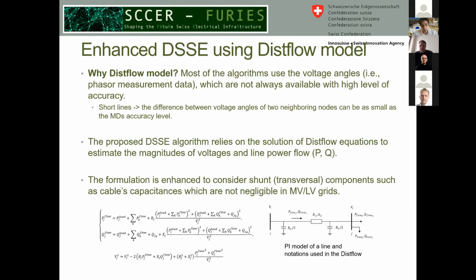The problem is that in low voltage networks, the lines are quite short, so the phase angle difference between two neighboring nodes can easily reach the accuracy level of the devices. So we developed the DSSE algorithm based on the dist flow model, which requires voltage magnitudes and power flow measurements.